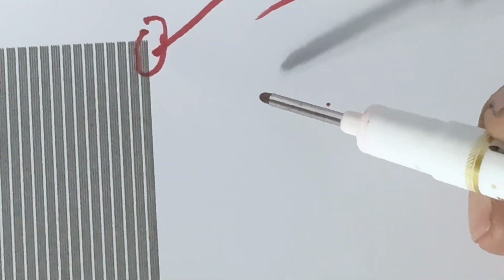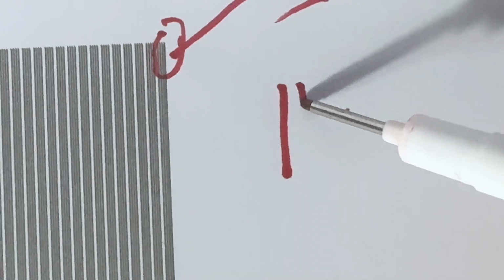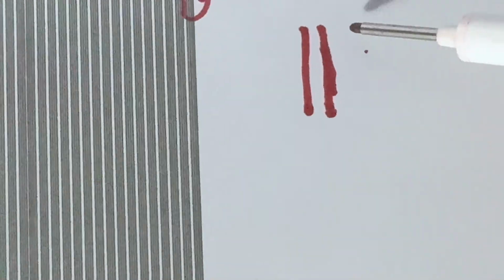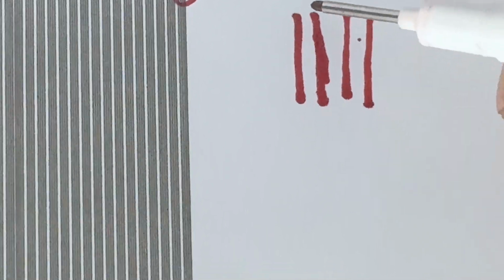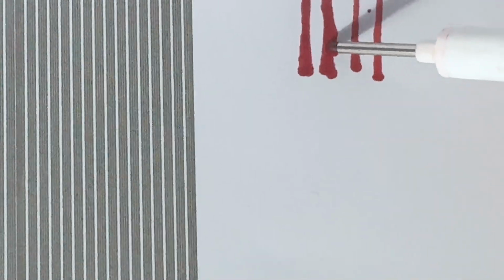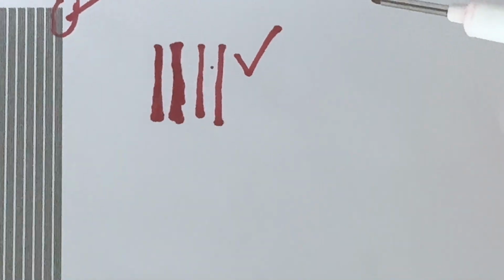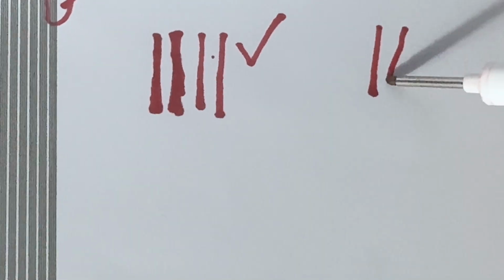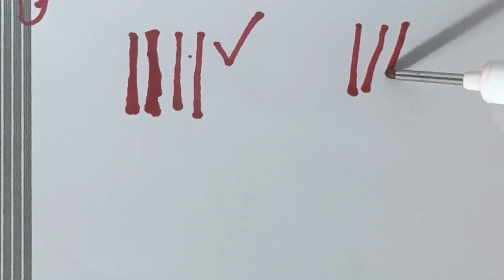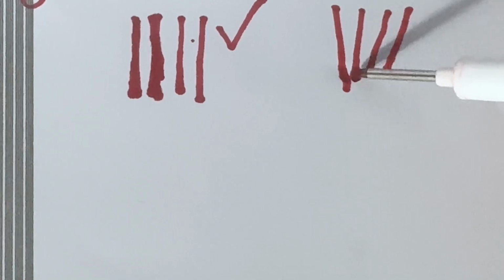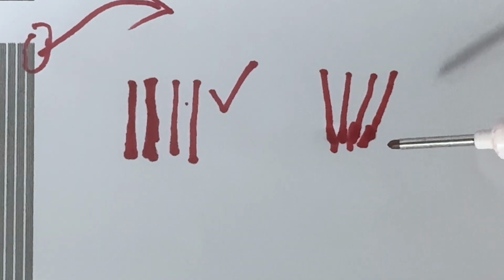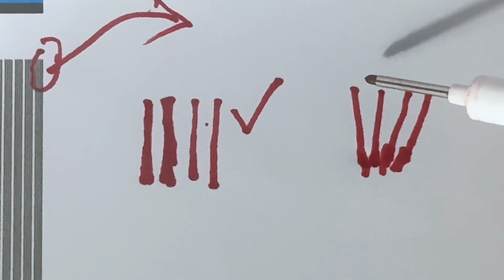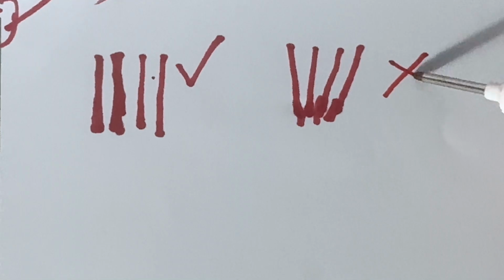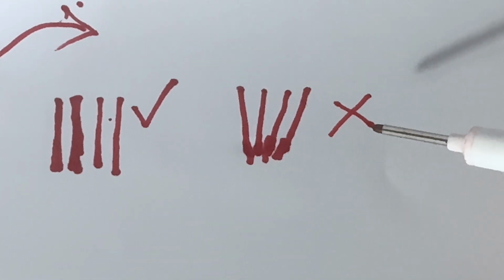The 4 lines must be exactly vertical and horizontal, like this. This is good. But if the print out image is like this, the gap at the top and at the bottom is different. So this is not good calibration for vertical. We need to do the calibration to adjust the print head.